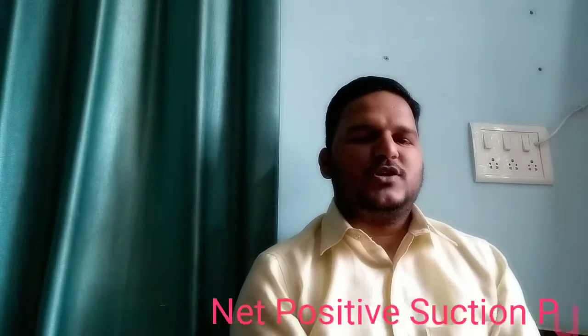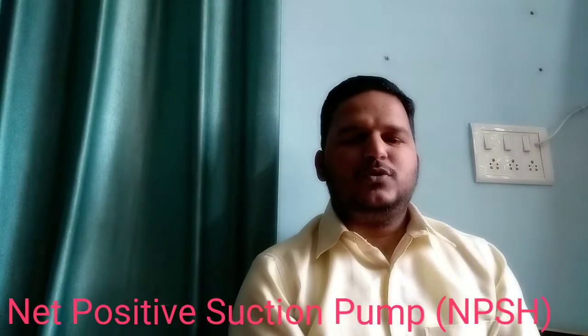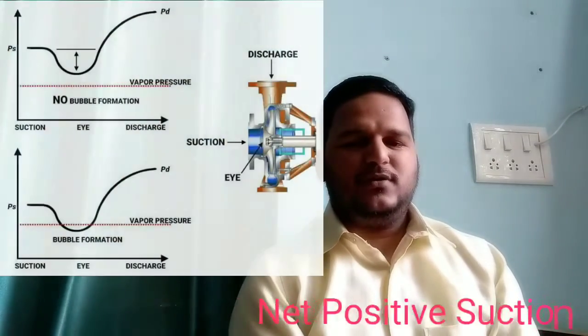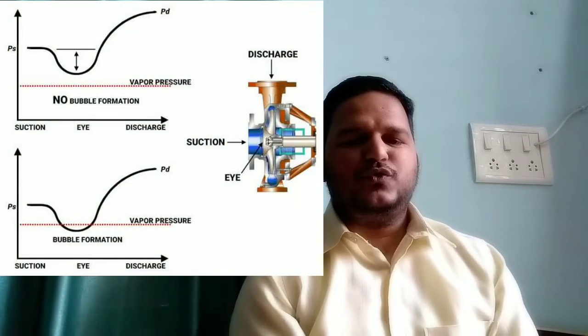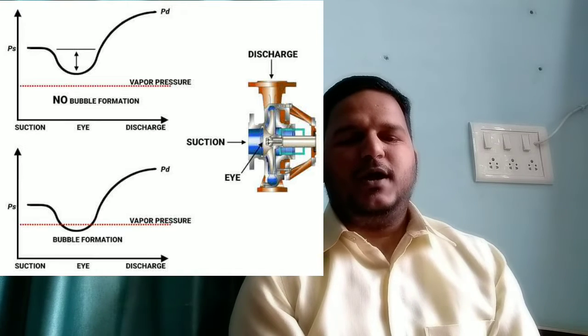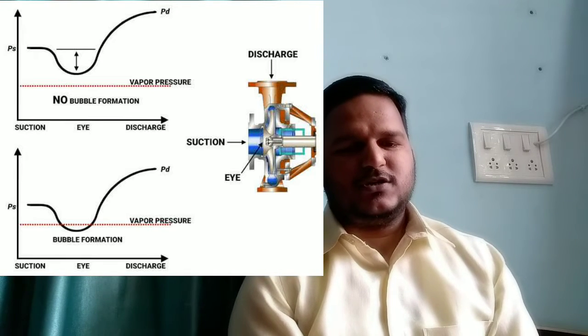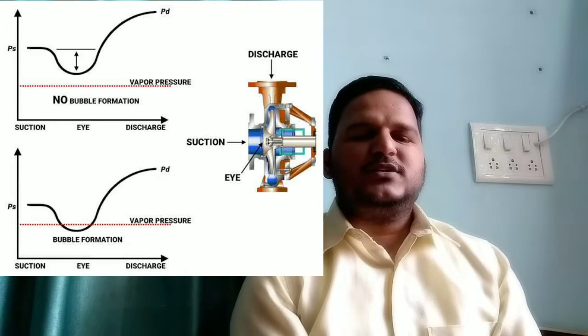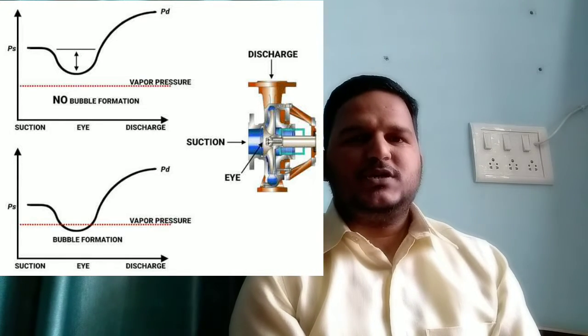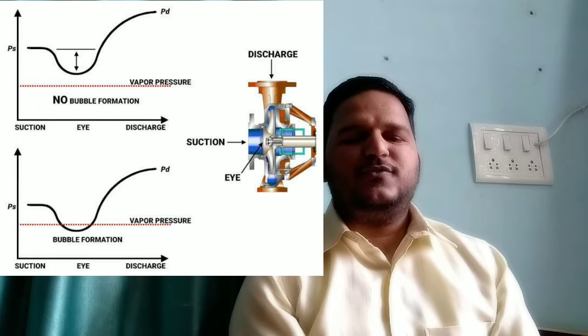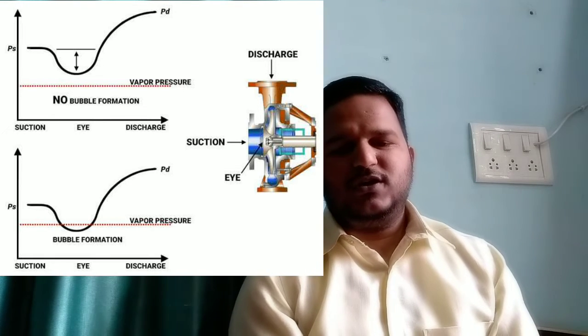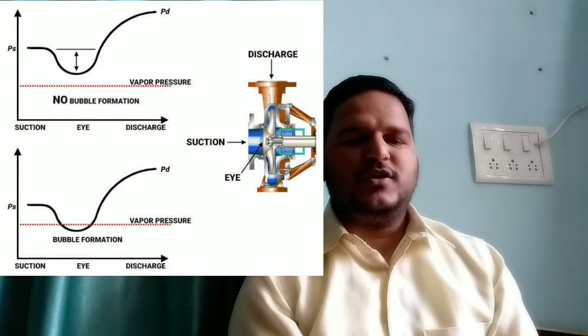The next term is NPSH, i.e. Net Positive Suction Head. It is the absolute pressure head at the inlet to the pump to force the liquid into the pump at a given temperature. It is necessary that NPSH is positive to avoid cavitation and force the liquid into the eye of the impeller.